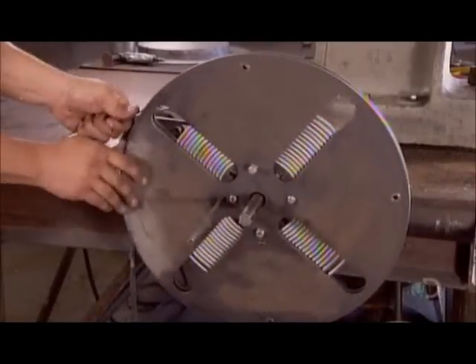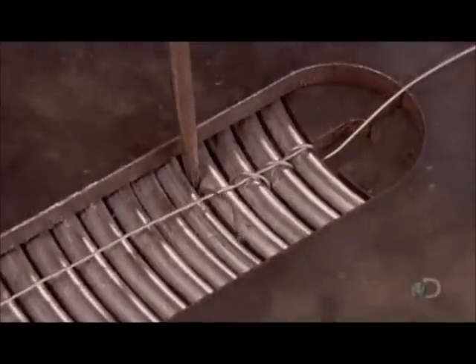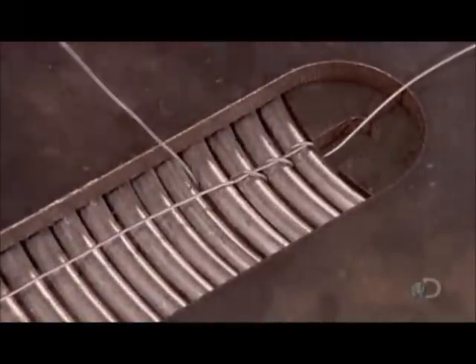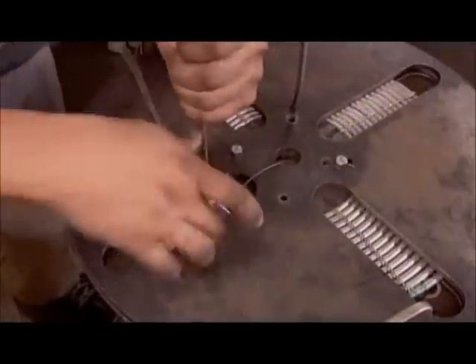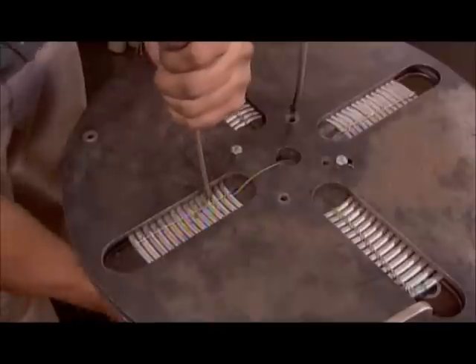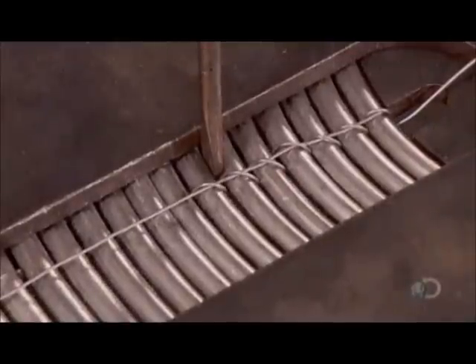They bind the coil with steel thread, putting a stitch in between each tube to create a minute gap. That way, when fuel burns in the combustion chamber, the heat can travel over and in between the tubes, heating the water inside faster and more efficiently than if the heat would contact only the coil's top and bottom surfaces.